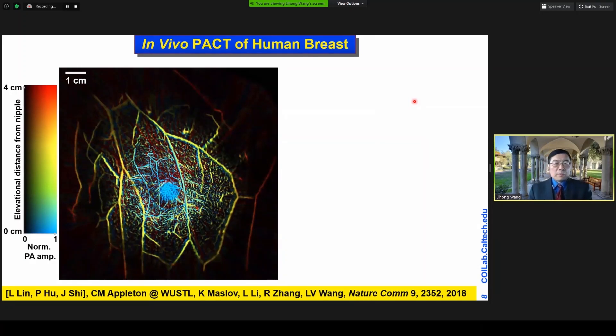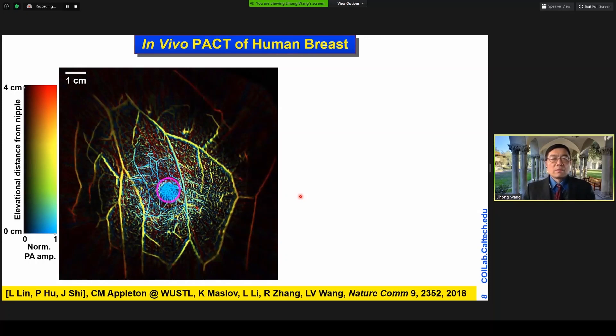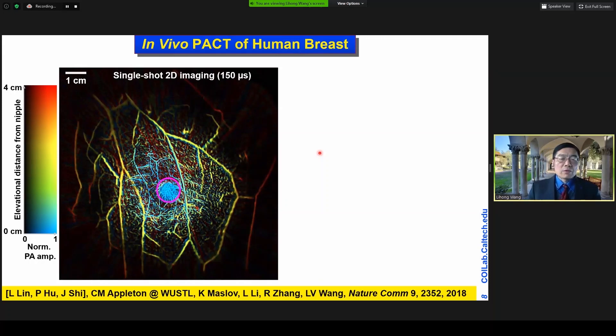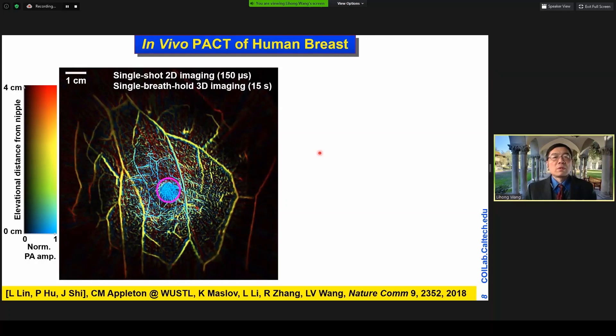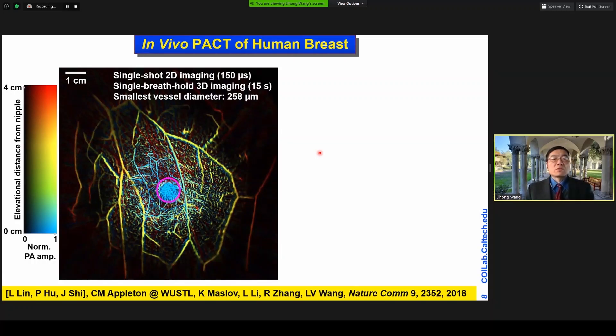We scaled up our system for human-scale imaging. This is one of the first images we acquired in human breast, in vivo. With a single laser shot, we can acquire a 2D cross-sectional image within 150 microseconds. Within a single breath hold — 15 seconds — we can acquire a full 3D image to minimize any breathing-induced motion artifact. The smallest vessel diameter we can image is a quarter of a millimeter, without injecting any exogenous contrast agents.